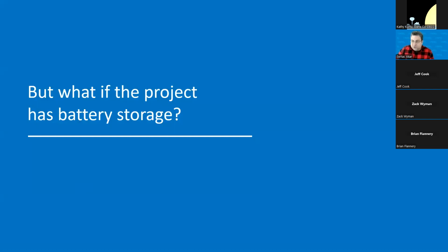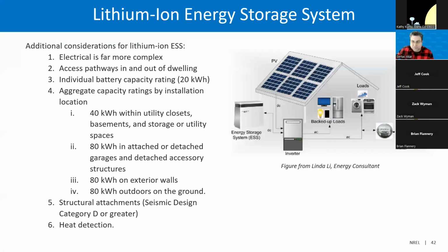But what if the project has battery storage? We have the same issue here. Battery storage systems require additional inspection processes. If the system has battery storage, the electrical structure of a PV system with a lithium-ion energy storage system is far more complex than a standalone PV system, which needs additional considerations and inspection processes. Additional inspections are required for individual battery capacity rating, aggregate capacity ratings by installation location, and heat detection.